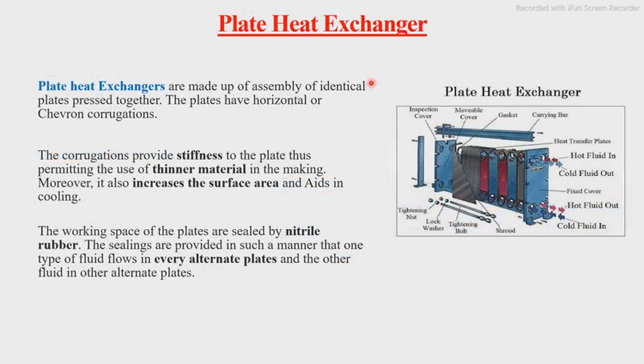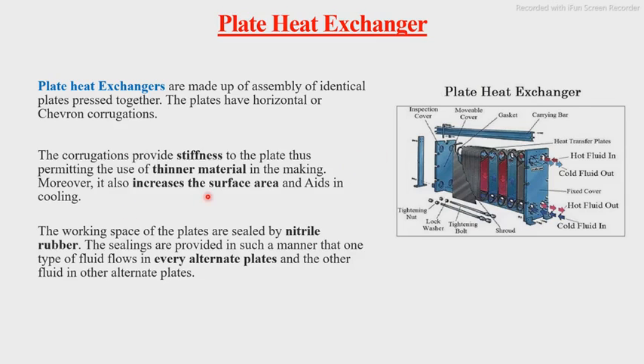Next we have plate type heat exchangers. Plate heat exchangers are made of an assembly of identical plates placed together. The plates have horizontal or chevron corrugations, as seen in this figure where various plates are pressed together. The corrugations provide stiffness to the plates, allowing use of thinner material while still withstanding the pressure generated. Moreover, corrugations also increase the surface area, which ultimately helps in efficient cooling.